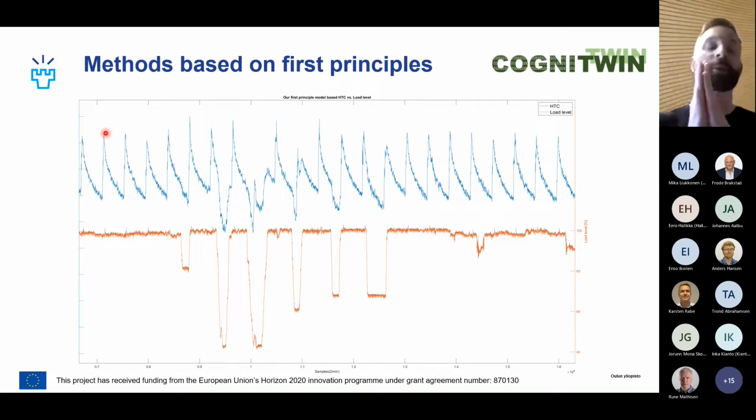So that means we increase the efficiency by soot blowing. So this jump up is represented by the cleaning operation. So in that case, the soot blowing operation, we clean the surface of the heat exchanger. We have high efficiency, and then via time, which is usually a 12-hour period, we degrade. So we lose the efficiency. And if we reach a certain minimal limit with the efficiency, then we inject again and clean, and so on and so on.